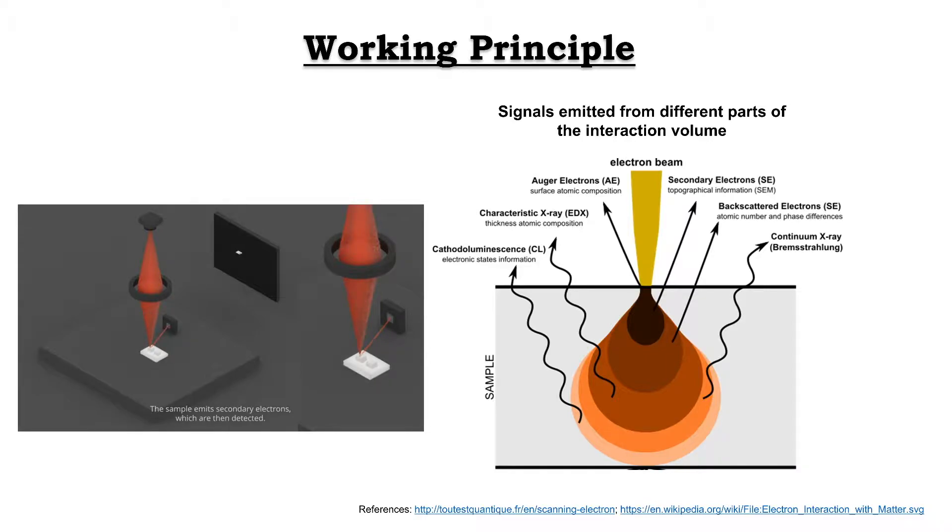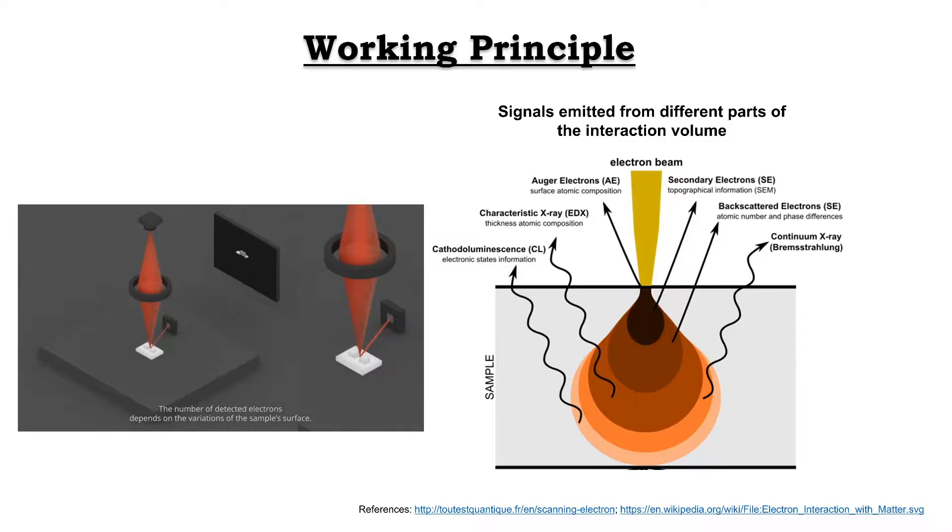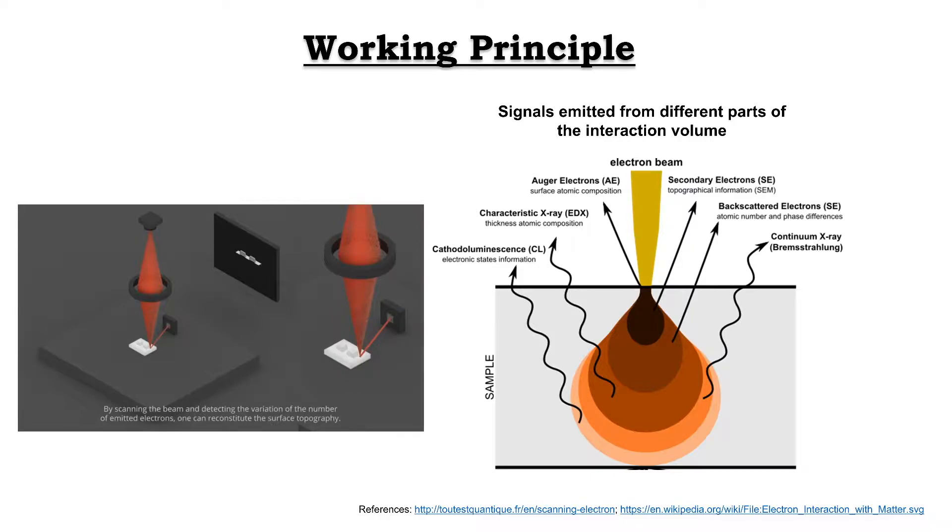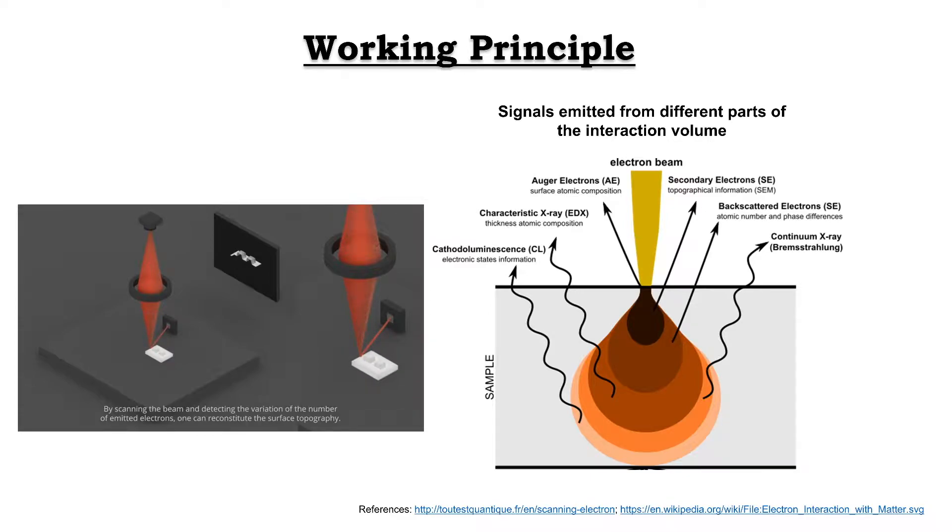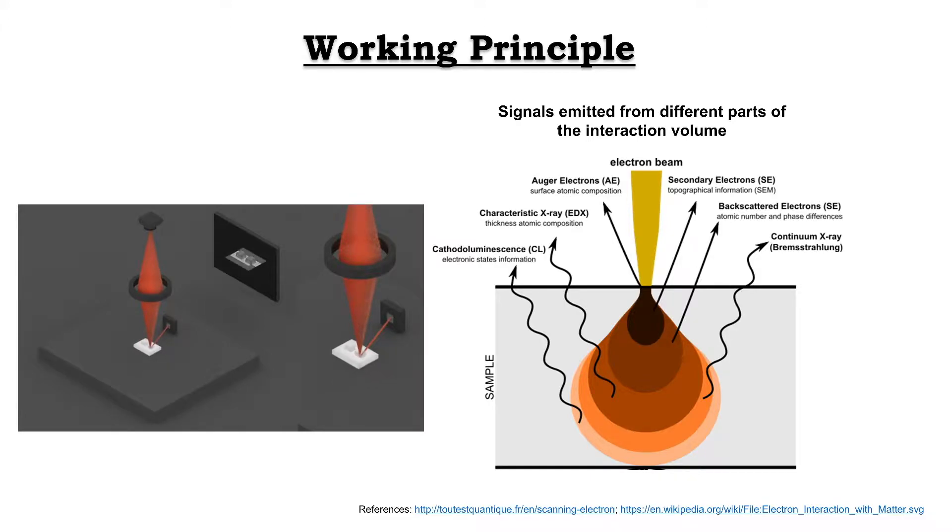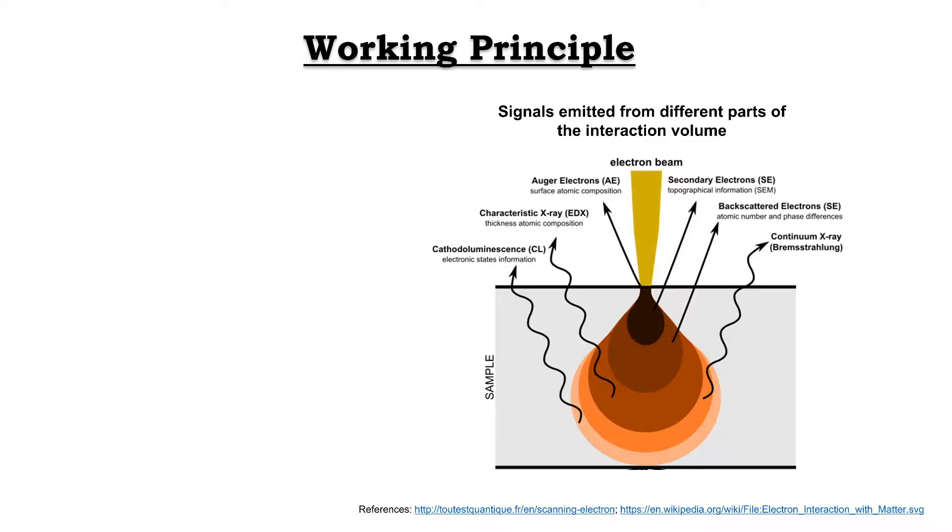First one is the secondary electron, then backscatter electron, then the X-ray electron. Secondary electron provides fine structure topographical features of the sample, and the backscatter electron discriminates areas of different atomic number elements. X-ray electrons are used to identify the composition and measure the amount of the elements in the samples.